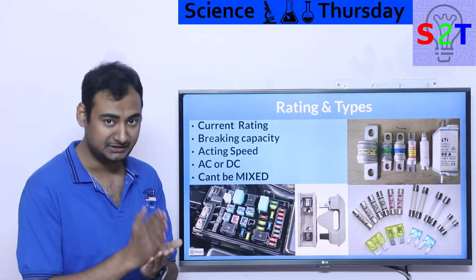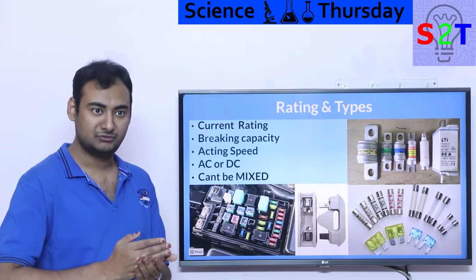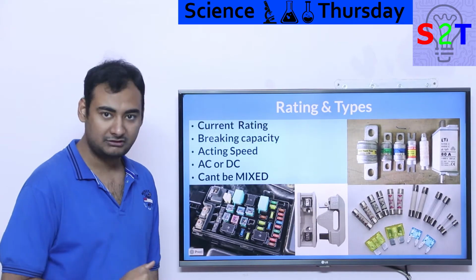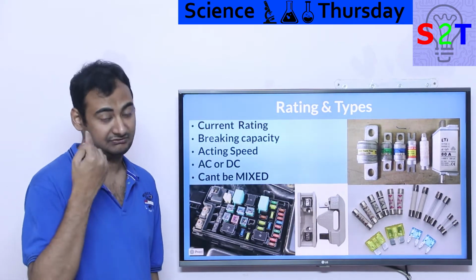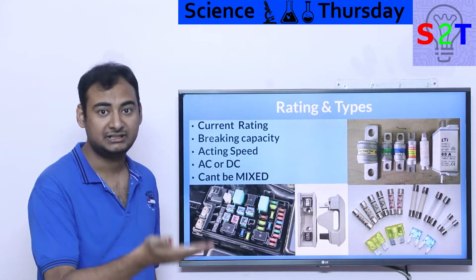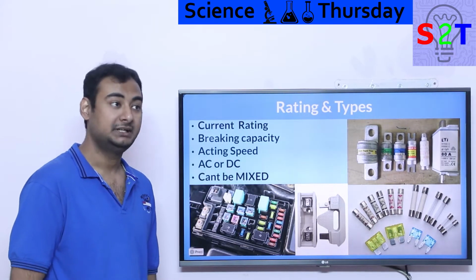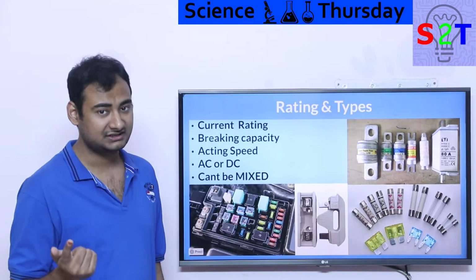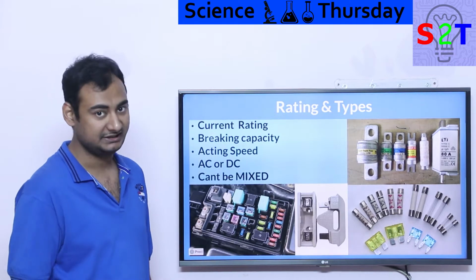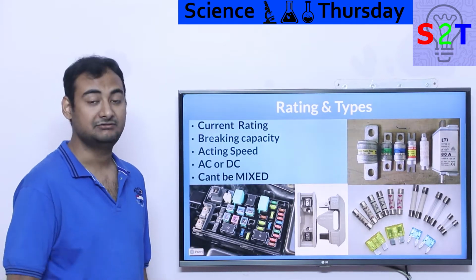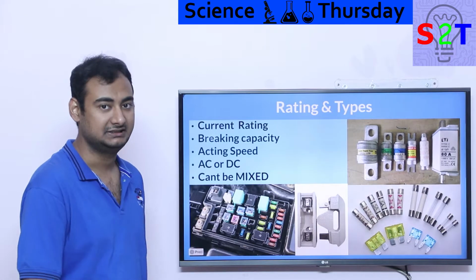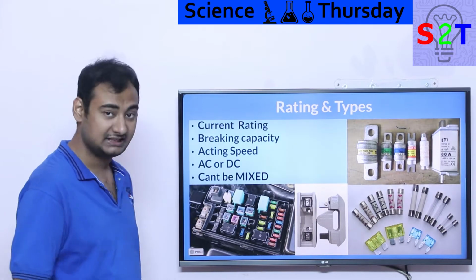Current rating is meant to handle 20, give it 20. The moment it exceeds 20, disconnect. Do not put a fuse of 10, or a fuse of 30, because if you put 30, overcurrent will happen and your equipment will be destroyed. It will still protect you in case of a short circuit, but not against overcurrent. So your equipment is at risk if you use overrated fuses.